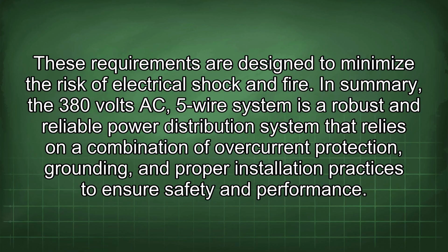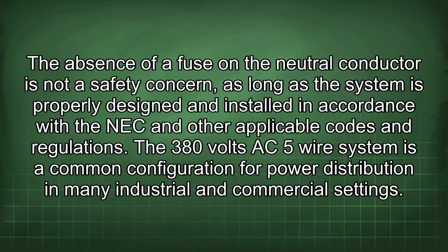In summary, the 380 volts AC 5-wire system is a robust and reliable power distribution system that relies on a combination of overcurrent protection, grounding, and proper installation practices to ensure safety and performance. The absence of a fuse on the neutral conductor is not a safety concern, as long as the system is properly designed and installed in accordance with the NEC and other applicable codes and regulations. The 380 volts AC 5-wire system is a common configuration for power distribution in many industrial and commercial settings.